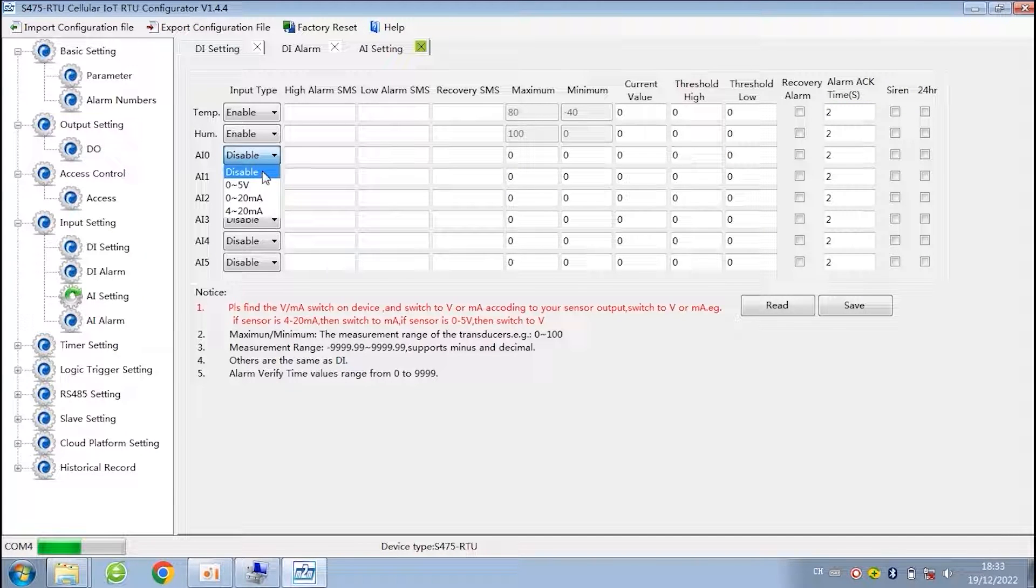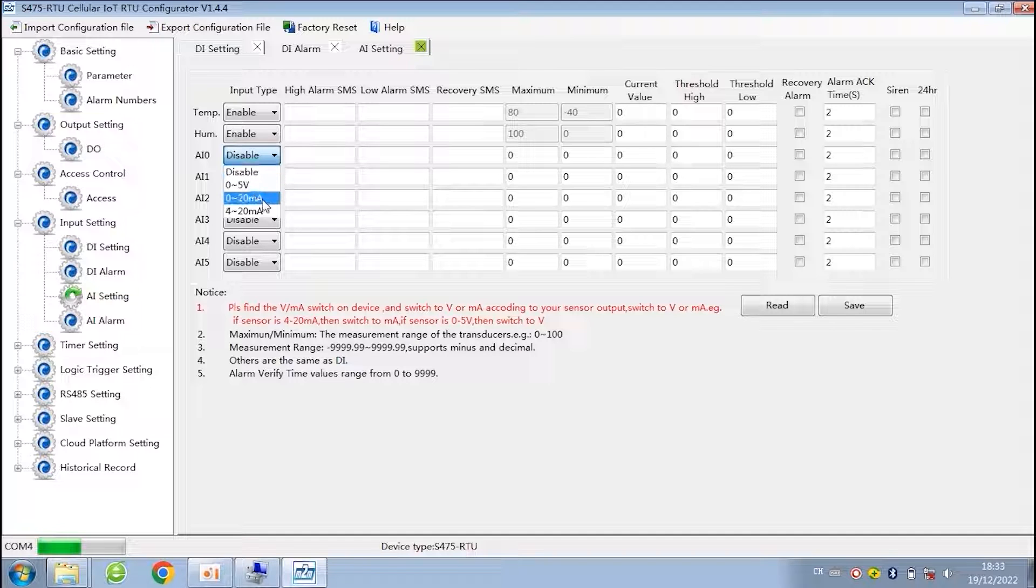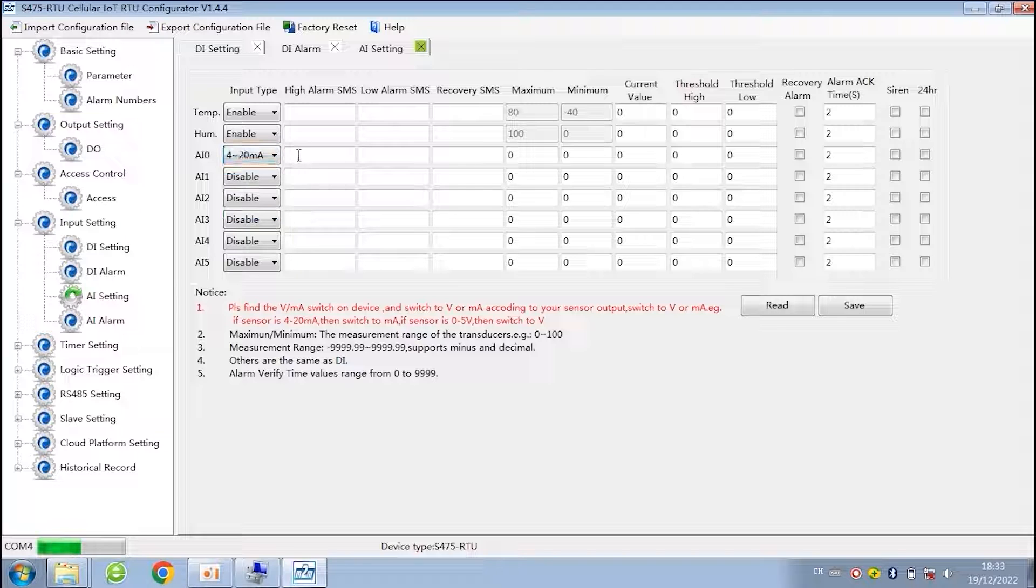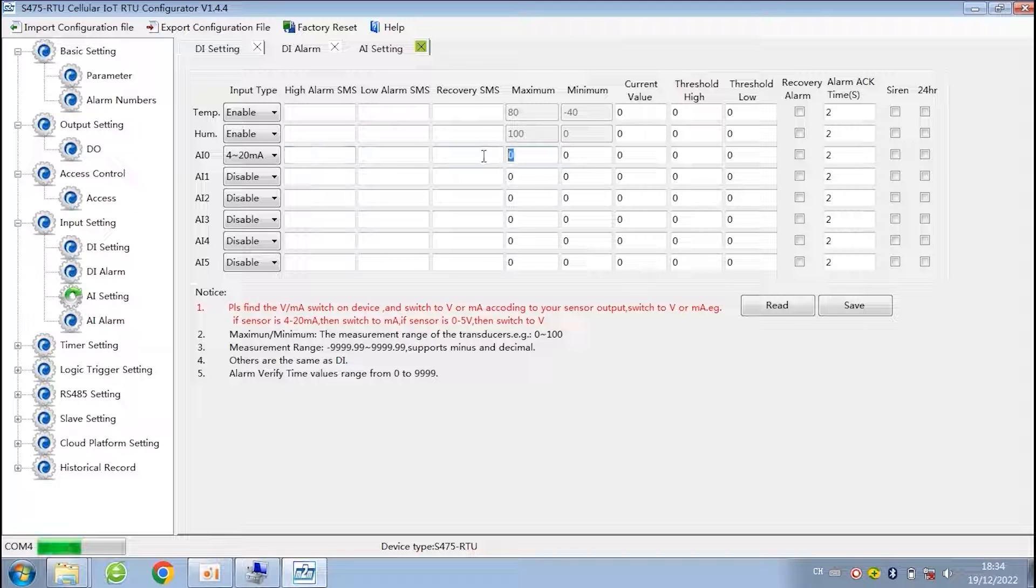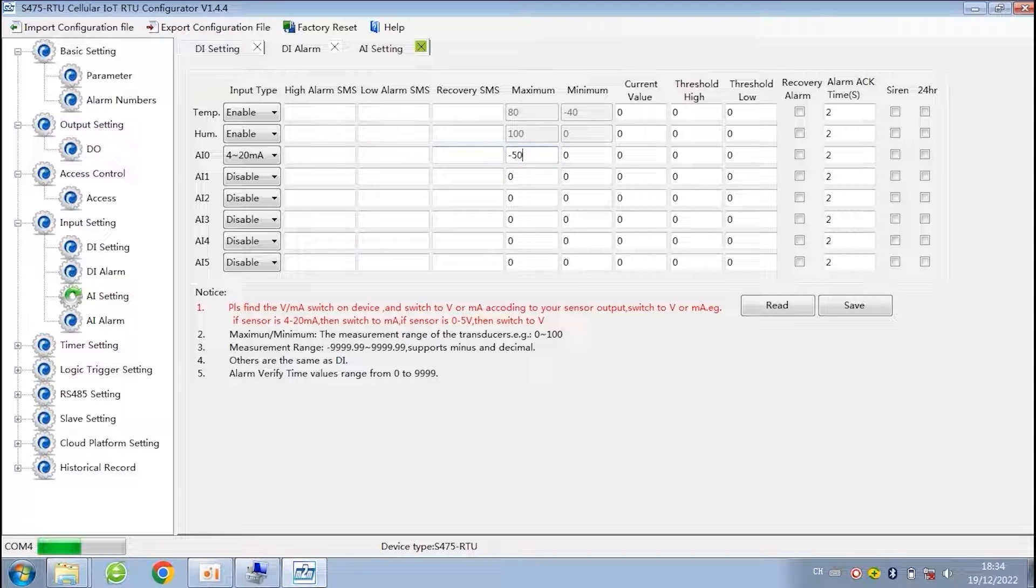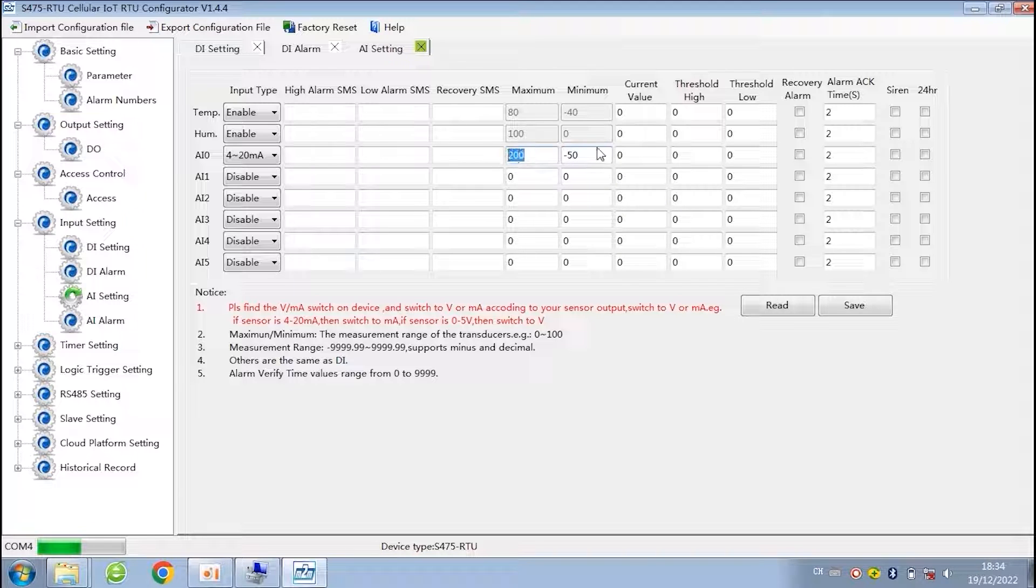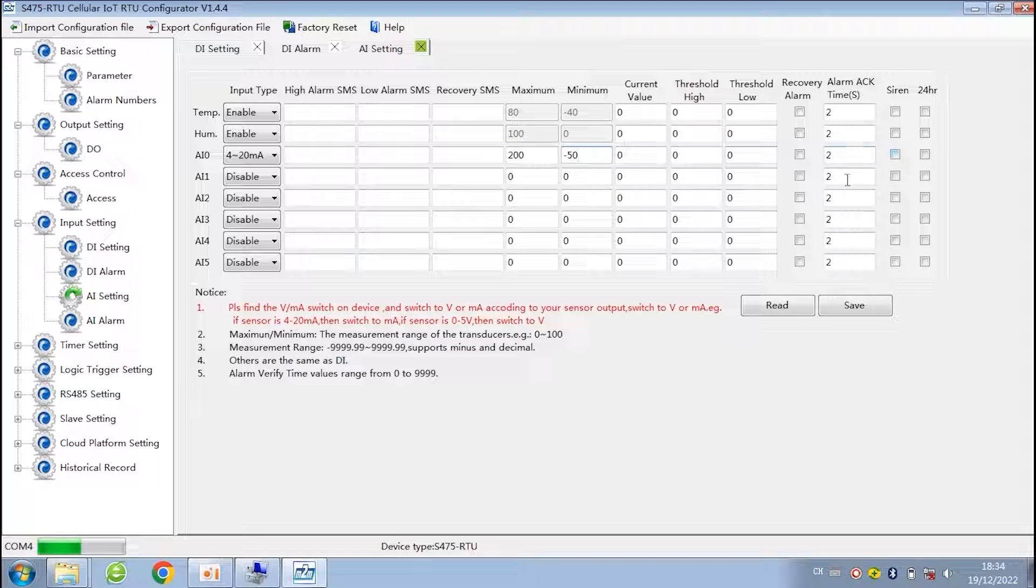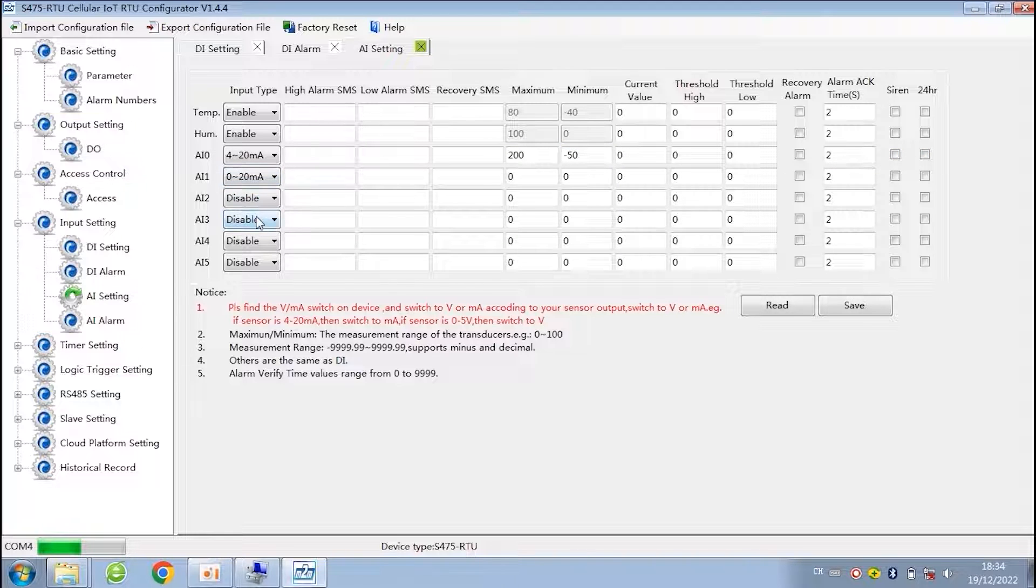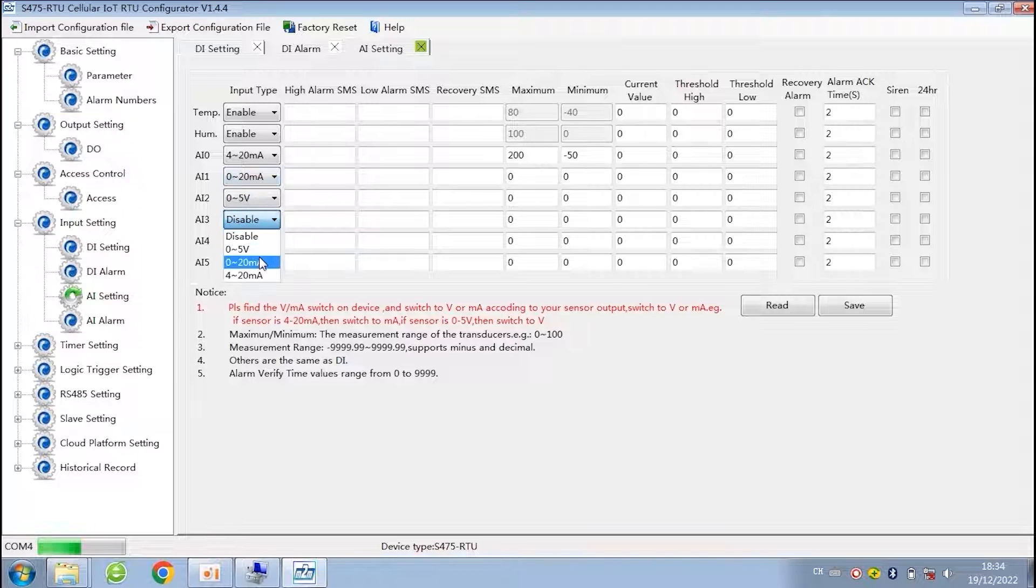Next are six channels analog input, support 0 to 5V, 0 to 20mA, 4 to 20mA. When the mode selected, it needs to be matched with the DIP switch on the device. And then set the SMS content, minimum and maximum value. For example, the range of your temperature sensor is minus 50 to 200. Then you enter the value according to the range. You can choose different mode for each channel according to the sensors.